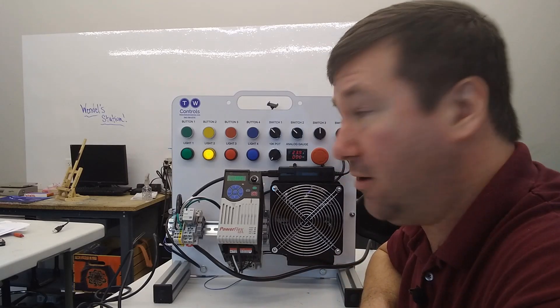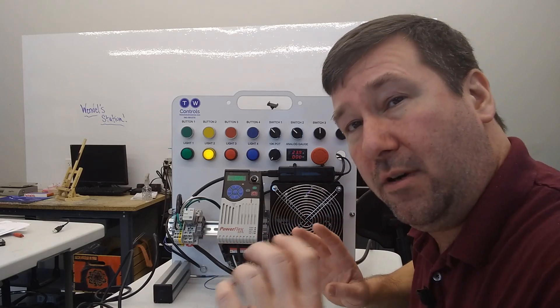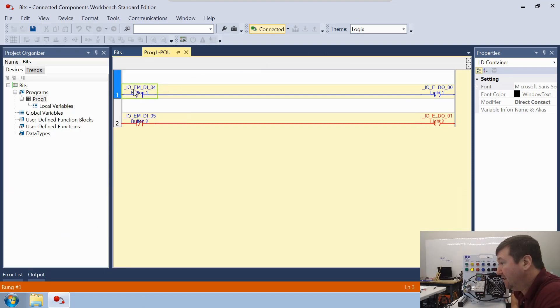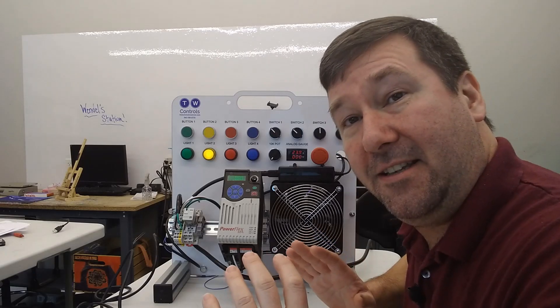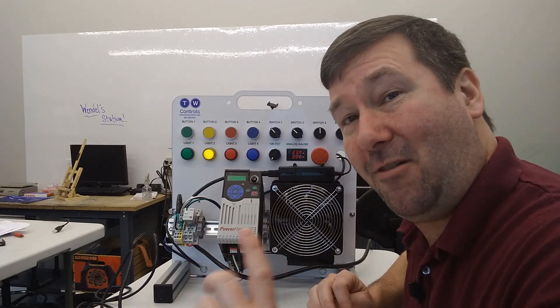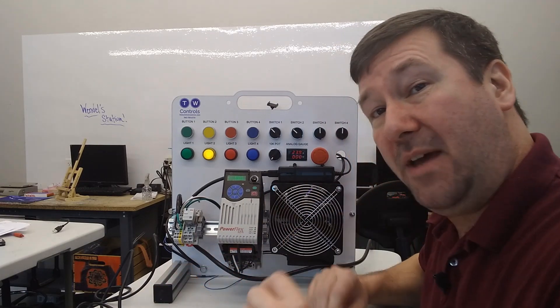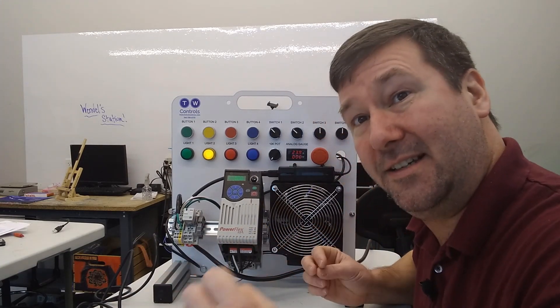That's the basics of this program, but there's a lot more here. This may be the most important thing to grasp if you really want to have a deep understanding of how PLCs operate. If we click on this button instruction it says Direct Contact; this output says Coil; this one says Reverse Contact. I'm going to tell you the most fundamental thing you need to comprehend: throw these three terms out the window. This is an attempt to make you relate a PLC to a contact or relay — but this isn't a relay, this is a PLC.